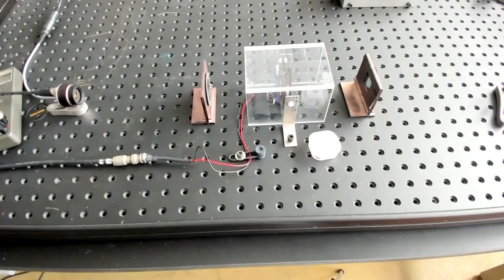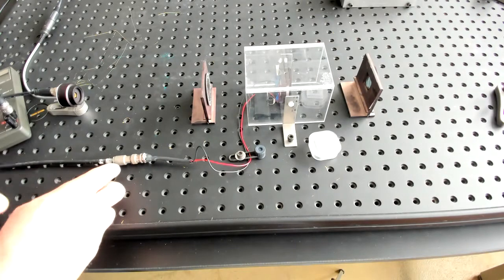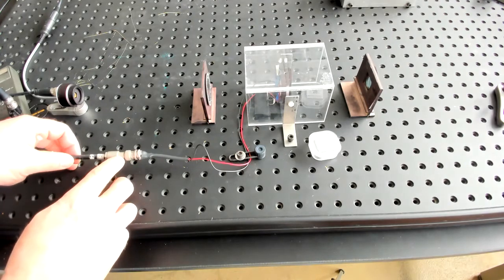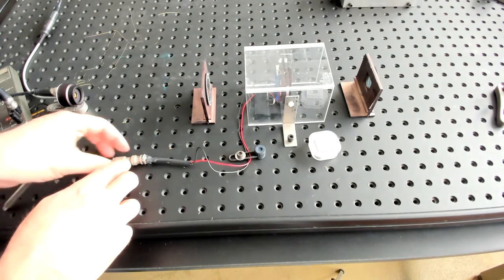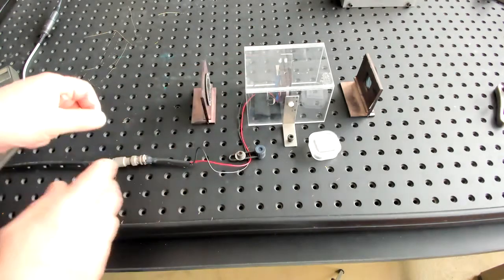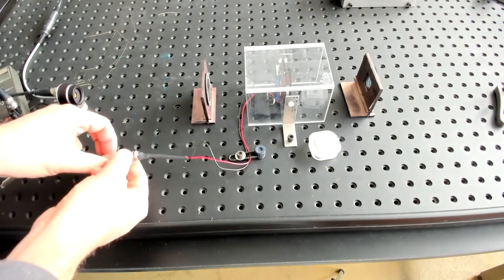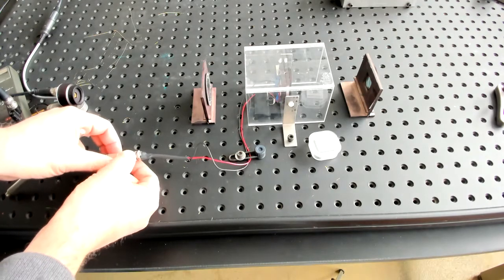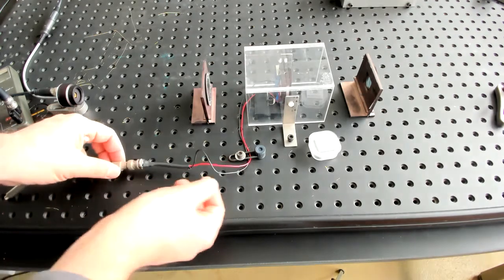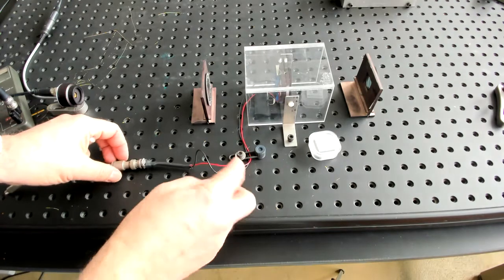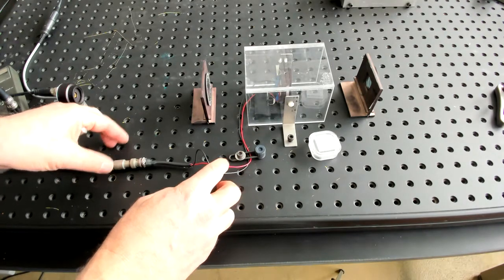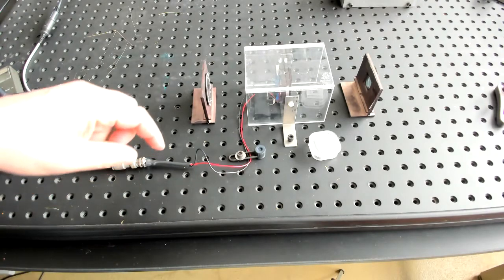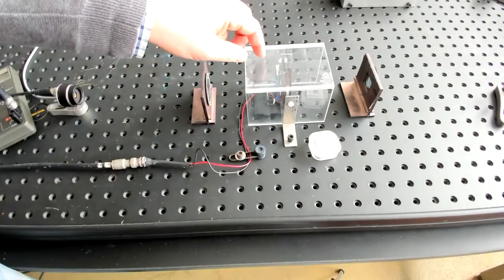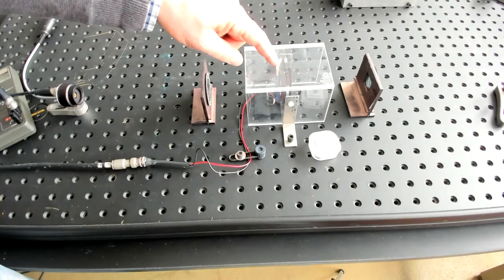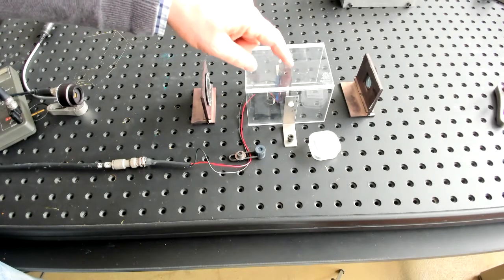Let's take a look at the other end of the wire. This is the other terminal for the high voltage BNC connector, and from here out are areas we have to be careful. The outside of this connector should be at ground, so it should be safe to touch. Likewise the black wire is at ground, but the red wire will be at high voltage. The red and black wires are just connected to terminals on the lithium niobate crystal.